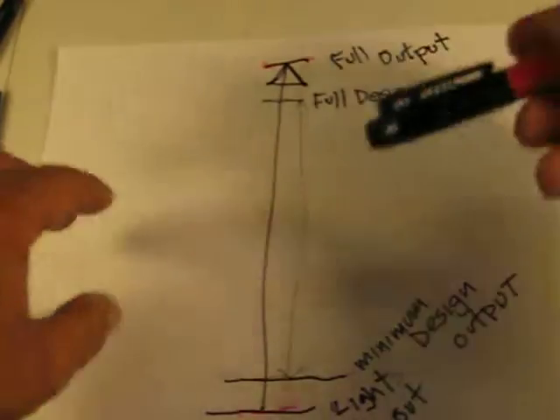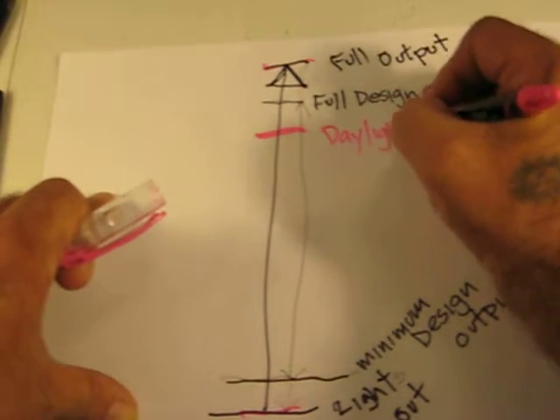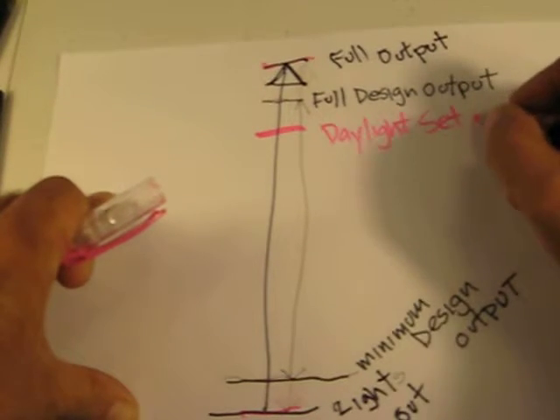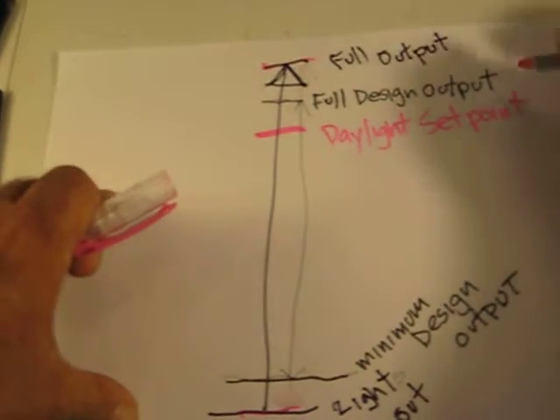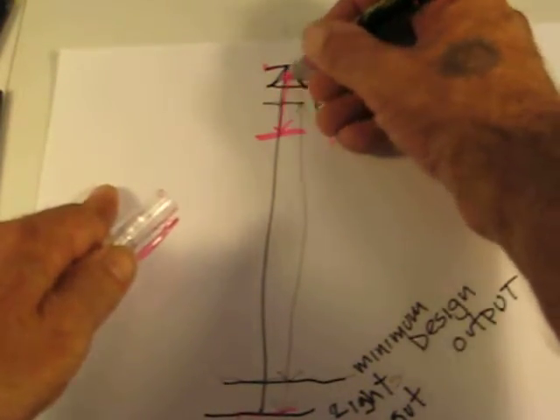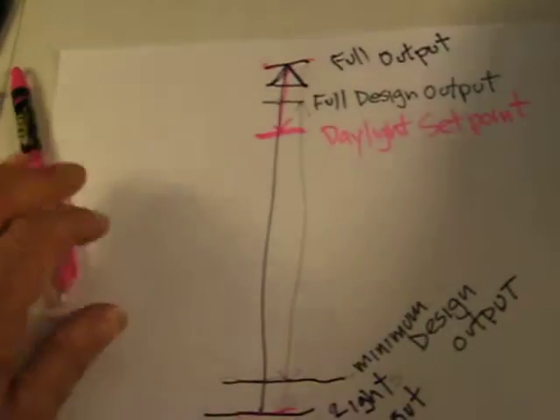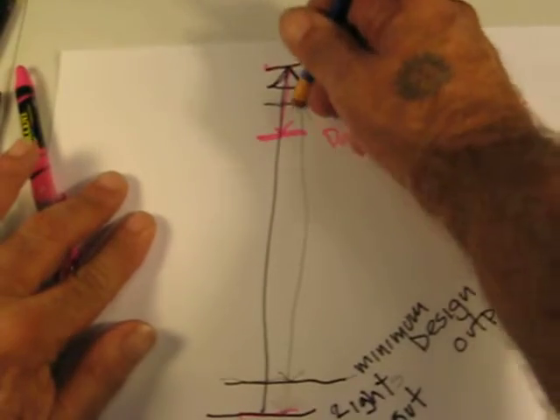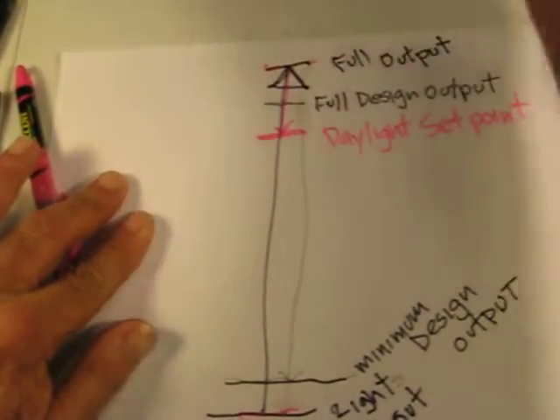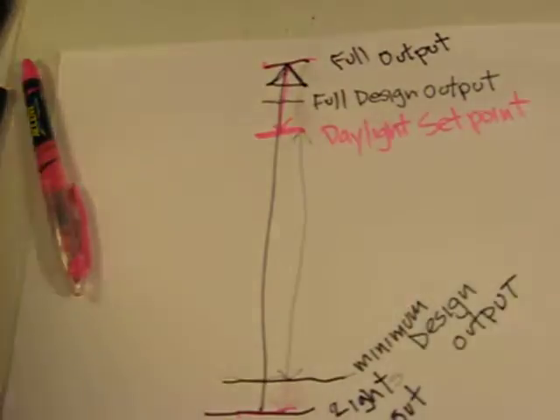But suppose we have a daylighting system in this area and daylight begins to come in. This gives us a daylighting set point — in other words, the point at which the electric lighting is being reduced in the area due to daylight coming in. If you have an automatic system, you are still required to have a manual dimming range that gets up to that set point.